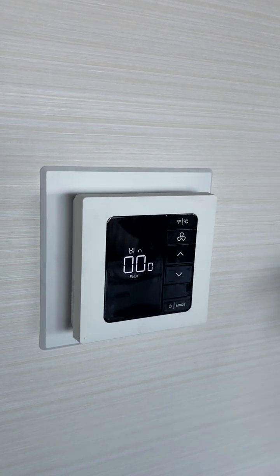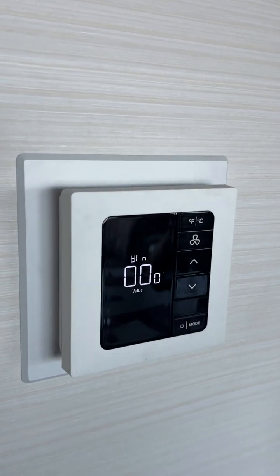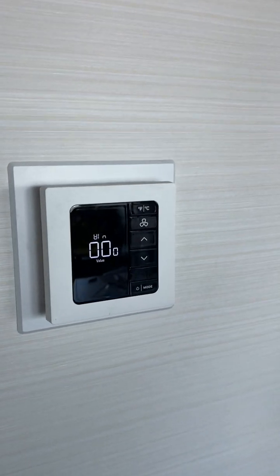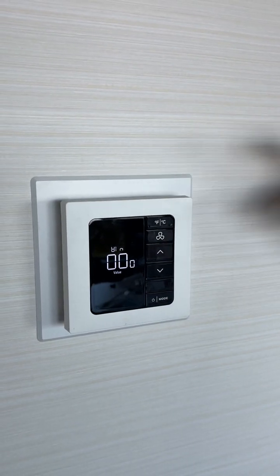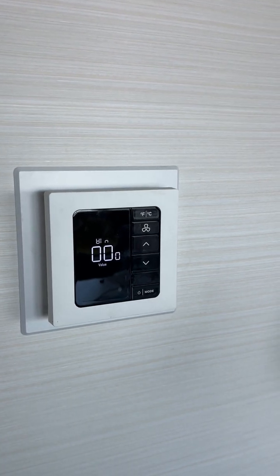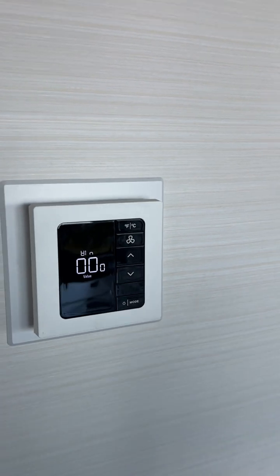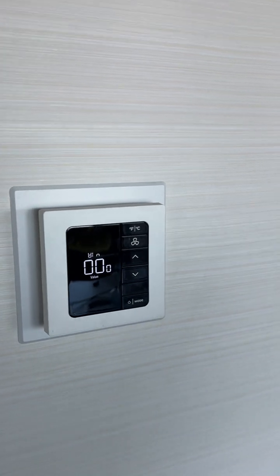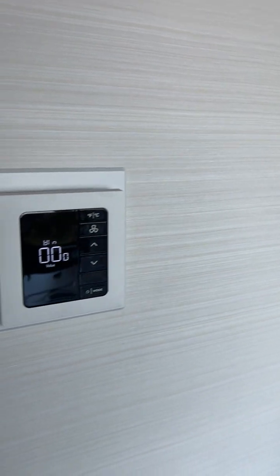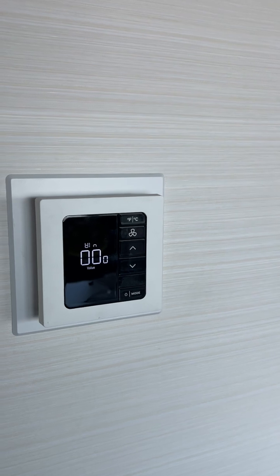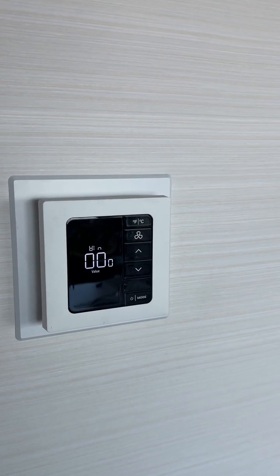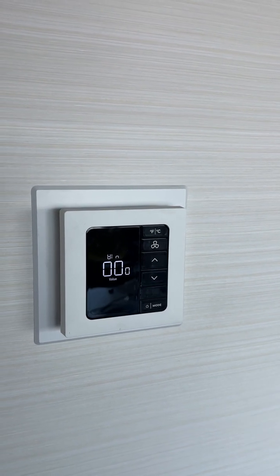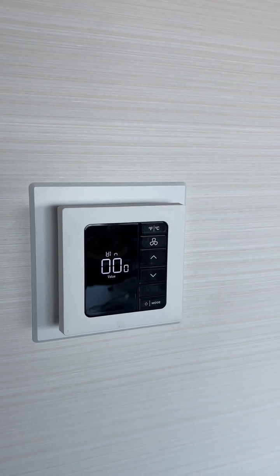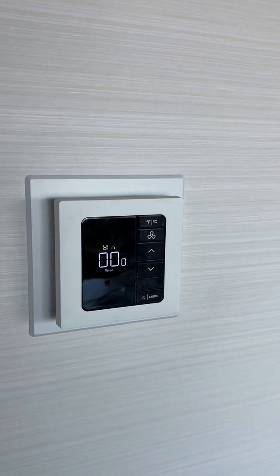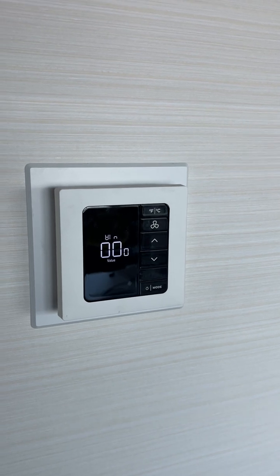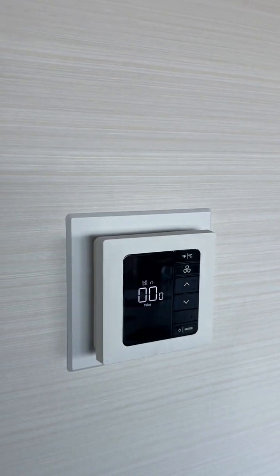Also, if the balcony is open, it'll lock down the thermostat after 30 seconds, and it'll show a little door icon on the thermostat. So if you see a little door icon and the thermostat's not working, close the balcony. And if the sensor turns out to be bad, we would put a new sensor in. If you don't have a new sensor handy, you could pull the batteries from the sensor and power cycle the thermostat, and it won't necessarily know it has a balcony door until it receives that first message. So you can disable it that way, killing the sensor temporarily while you're waiting for a replacement.